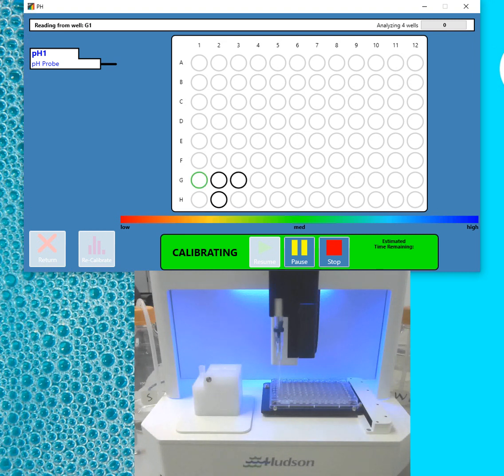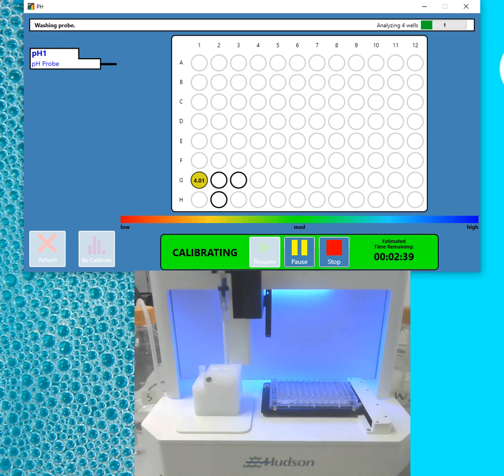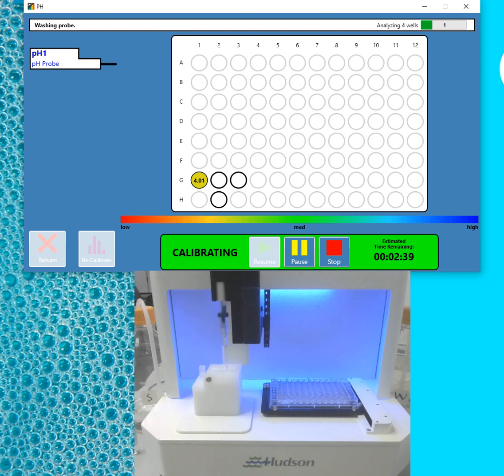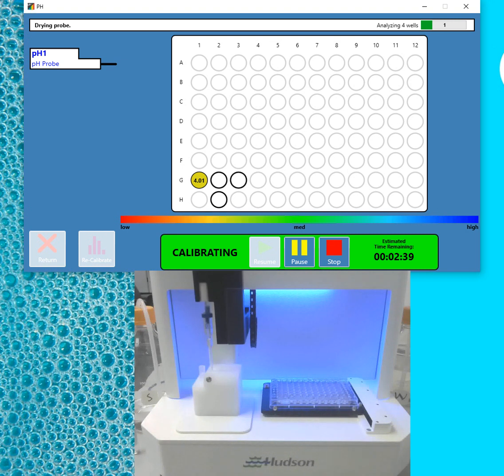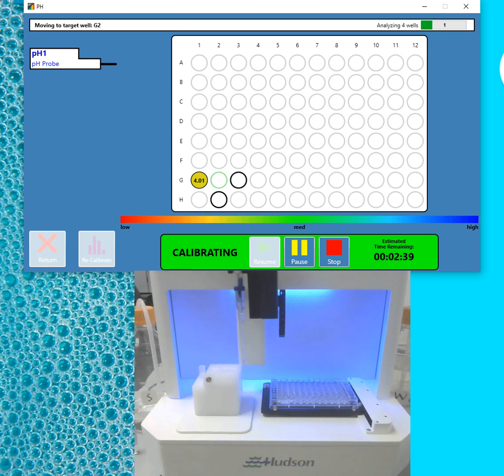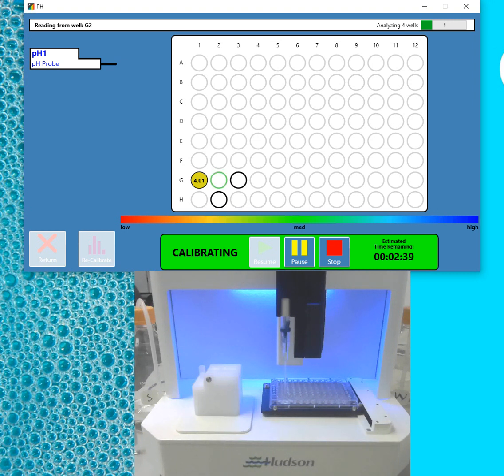So while it's picking the sample reading, I'll discuss the minimum volumes. So in a standard microplate with a flat bottom, we recommend 200 microliters. In a rounded bottom plate, you can use 150 microliters. And in a half-diameter plate, we recommend 75 microliters. We're currently using the InLab Micro Probe. So this probe is rated at 45 microliters, which we have tested successfully. But because each plate can be slightly different, and basically there can be errors in the pipetting technique, we do recommend 75 microliters as your minimum.